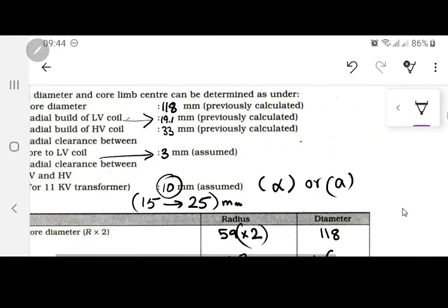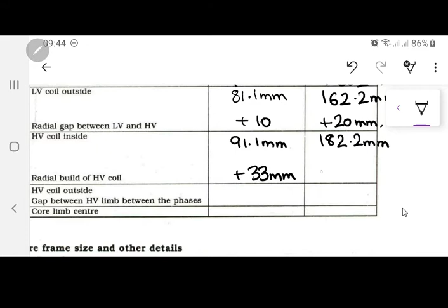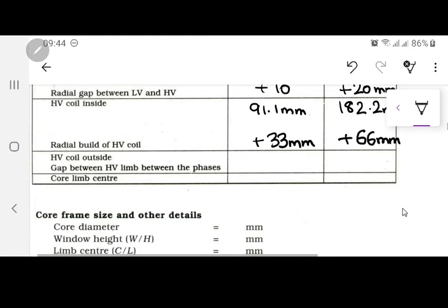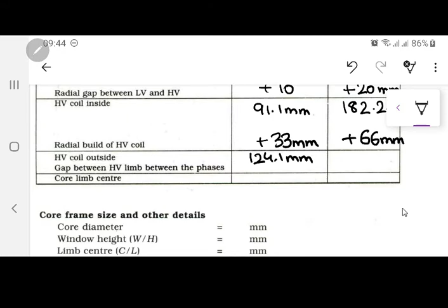So the radial build of the high voltage coil, if you go back, that was 33 mm. So this means this is going to be plus 33 over here, and here this will be plus 66 mm. So the high voltage coil outside becomes - please add this to 124.1, and add these two - this will become 248.2 millimeters. Okay, gap between high voltage limb between the phases - this is very important.